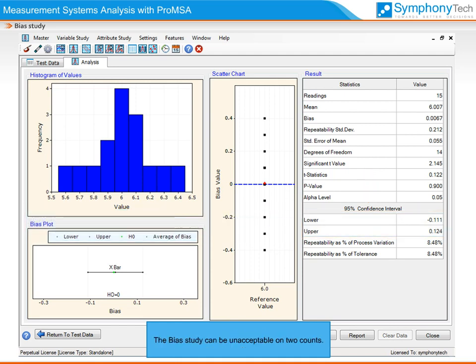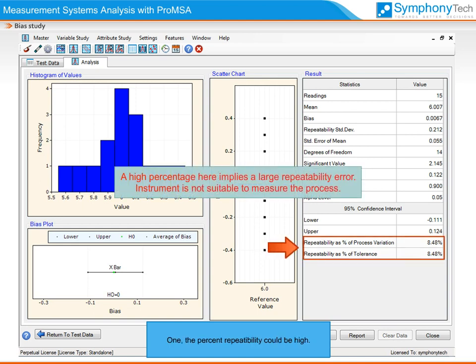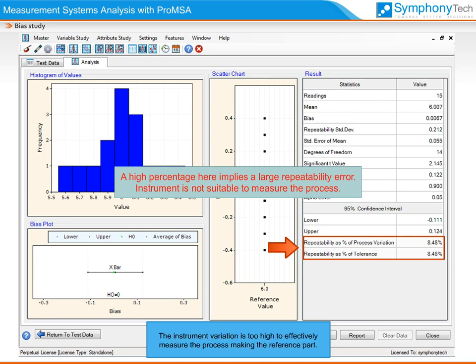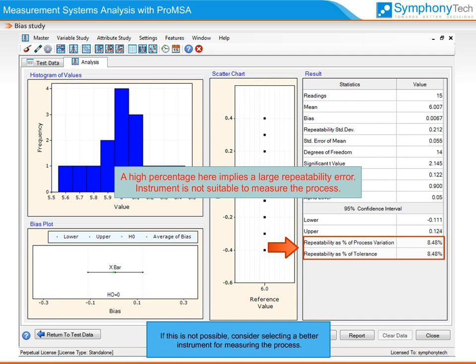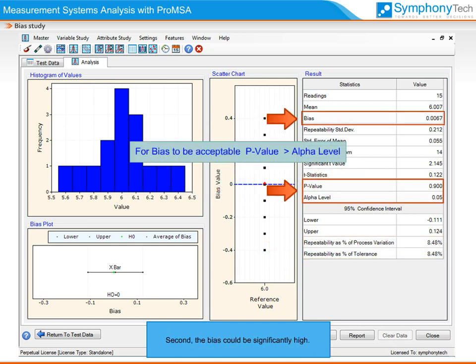The bias study can be unacceptable on two counts. First, the percent repeatability could be high — the instrument variation is too high to effectively measure the process making the reference part. In such a case, the instrument may require maintenance or calibration to improve its repeatability. If this is not possible, consider selecting a better instrument. Second, the bias could be significantly high, which can usually be corrected by calibration.